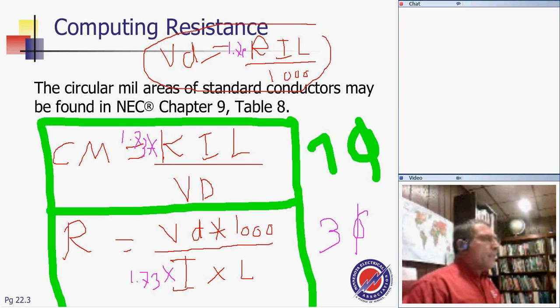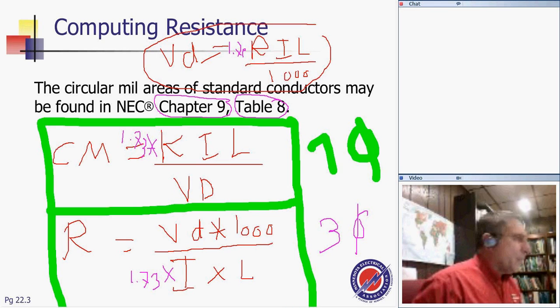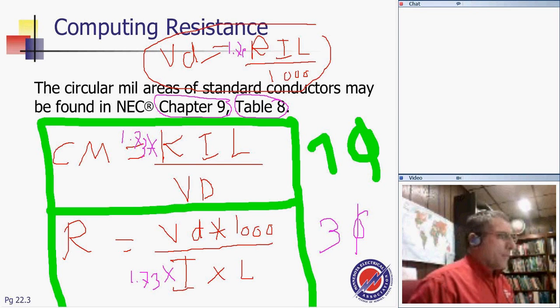What do you guys think about these two very important formulas to size based on voltage drop? Any more math questions? Now you find the R in table number 8, guys. The DC resistance table gives you DC resistance for all the gauges approved by the NEC book. It's in Chapter 9. We'll check into that in a second. But the most important thing is knowing these formulas.